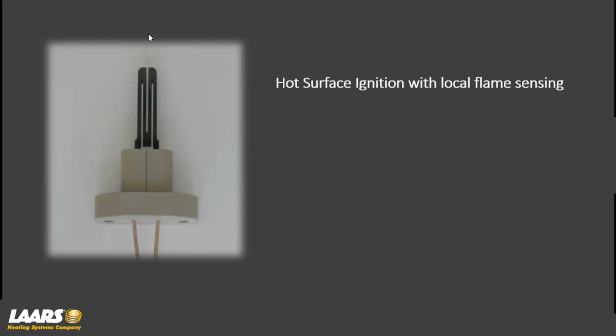So again, it glows cherry red. Your filament will go cherry red, and that filament will be in the top of the flame. So we're changing the resistance and we're picking up the grounding signal through the flame. And that's how we do rectification. You have 4-second trial for ignition. So we energize the igniter. That goes through its glowing period, call that 20-second warm-up period, gets cherry red, nice and hot, and then we'll energize a gas valve. We'll go through that sequence today as well.